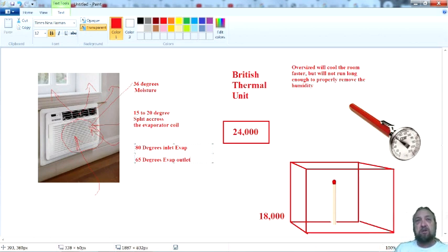If you could tell the customer these two things before you make the test, and they're allowed to see and touch the evaporator, there you show them the temperature of the air coming in, the temperature coming out, and it met the 15 to 20 degrees, and you told them this is what I'm looking for before I even start, they can't argue with you. You told them this is what a good working air conditioner does. Then the customer's going to say, well, it still ain't cooling. The reason why that's happening, ma'am or sir, is because your unit is not big enough to remove the heat as fast as the heat's coming in. All right? Do you understand those things?